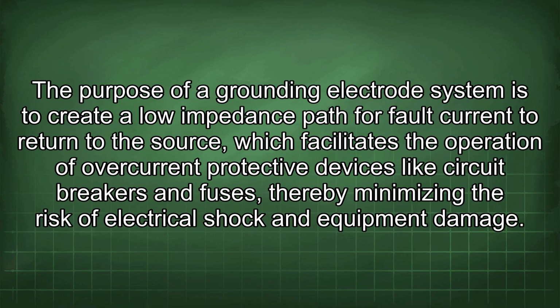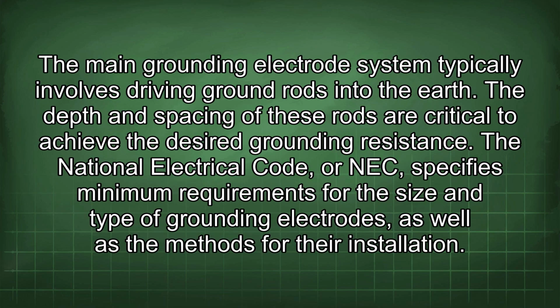The purpose of a grounding electrode system is to create a low impedance path for fault current to return to the source, which facilitates the operation of overcurrent protective devices like circuit breakers and fuses, thereby minimizing the risk of electrical shock and equipment damage. The main grounding electrode system typically involves driving ground rods into the earth. The depth and spacing of these rods are critical to achieve the desired grounding resistance.